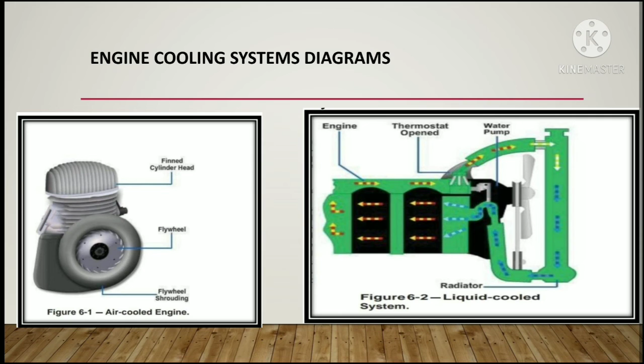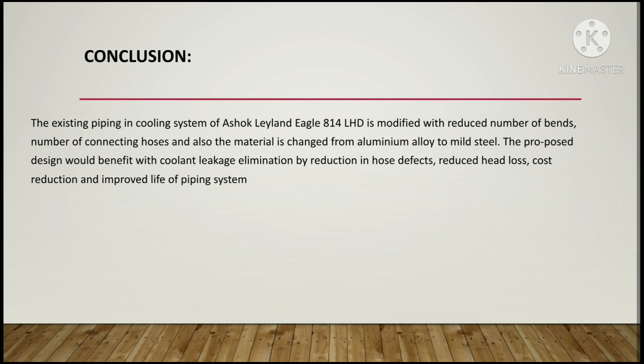Conclusion. The existing piping in the cooling system of the Ashok Leyland Eagle 814 LHD is modified with a reduced number of bends and connecting hoses, and the material is also changed from aluminum alloy to mild steel. The proposed design would benefit by eliminating coolant leakage through reduction of hose defects, reduced head loss, cost reduction, and improved life of the piping system.